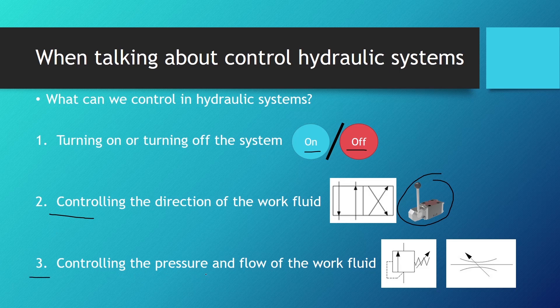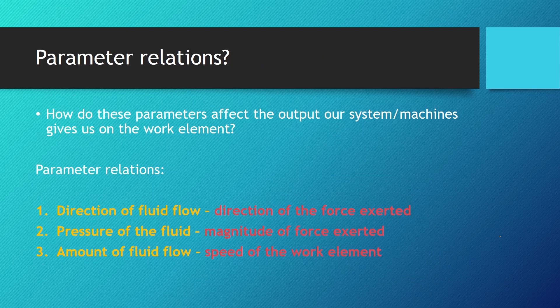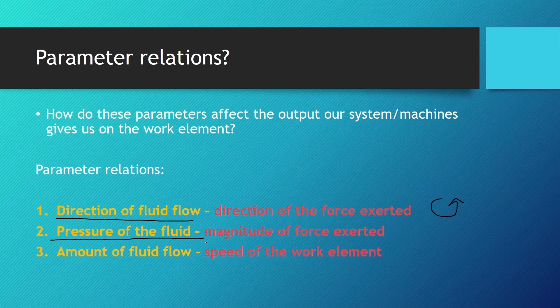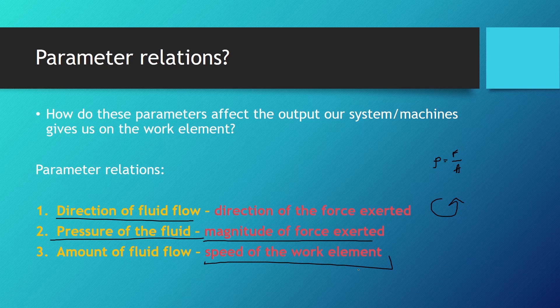Third would be controlling the pressure and flow of the work fluid. Here we can see a pressure relief valve, and here we can see the flow control valve. Changing the direction of fluid flow changes the direction of the force exerted, or torque if we're talking about rotational hydraulic motors. Changing the pressure affects the magnitude of the force exerted — pressure is equal to force divided by area. And the amount of fluid flow will directly influence the speed of the work element at the output, as the speed equations were always influenced by fluid flow.